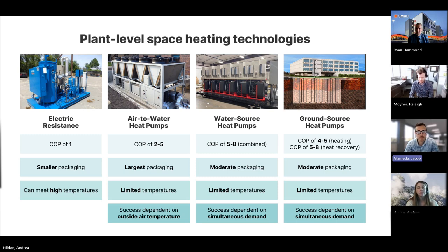But the downside to air-to-water heat pumps is they're kind of like air-cooled chillers. They're large, they're heavy, and they need to be outdoors with access to the air as a heat source. This means it takes some creativity to utilize these on existing buildings that are currently set up with a gas boiler tucked into a closet that's small, lightweight and quiet. Another downside with air-to-water heat pumps is you don't really want to design them with a supply temperature above 130 degrees or so, and I'll talk a little bit more about that on the next slide.